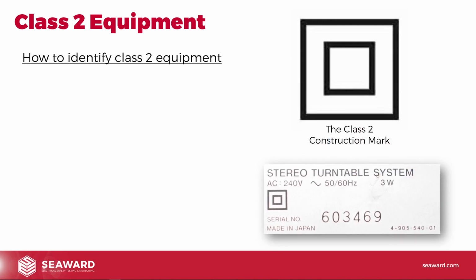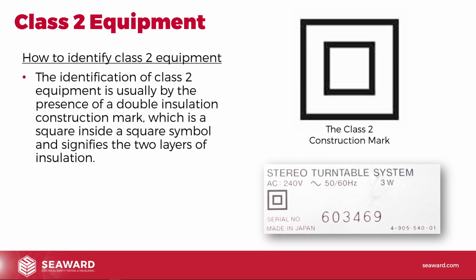So how do we identify class 2 equipment? The identification of class 2 equipment is usually by the presence of the double insulation construction mark. So you'll see on the right hand side there we've got the double insulation construction mark, that box inside a box, and underneath the mark you'll actually see an example of a rating plate from a stereo turntable system, and you'll see displayed on the rating plate that double insulation mark.